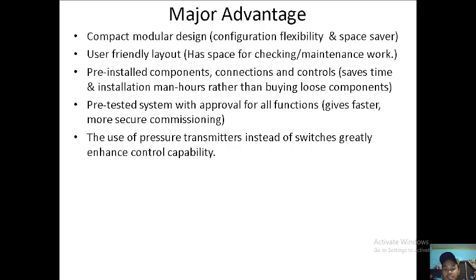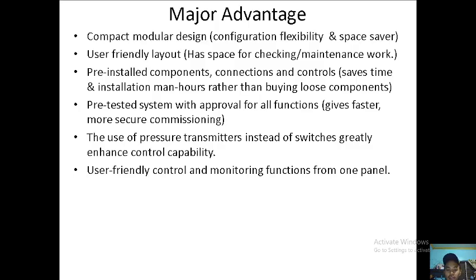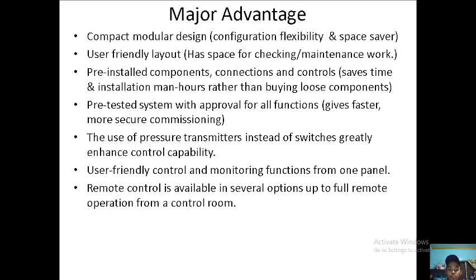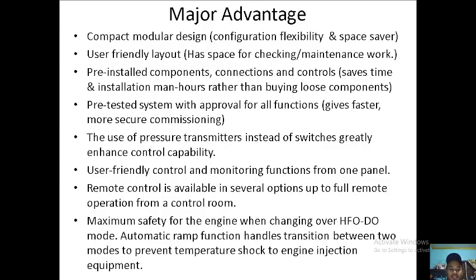Next, the use of pressure transmitters instead of switches greatly enhances control capability. We have user-friendly control and monitoring functions from one panel, so you don't have to go to different panels to monitor your system. Just one panel. We also have remote control, which is available in several options, up to full remote operation from a control room. It depends on the owner. And then it has maximum safety for the engine with changing over from HFO to DO mode. The automatic ramp function handles the transition between the two modes to prevent temperature shock to the engine injection equipment.